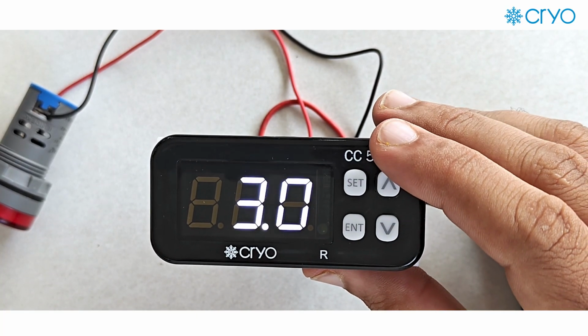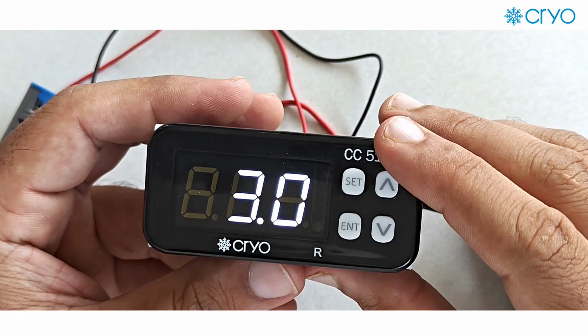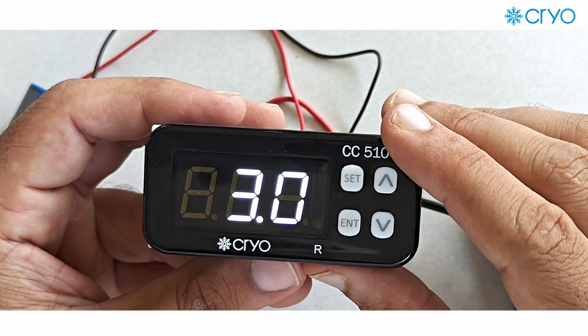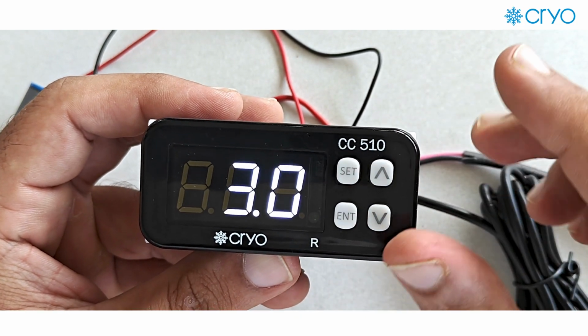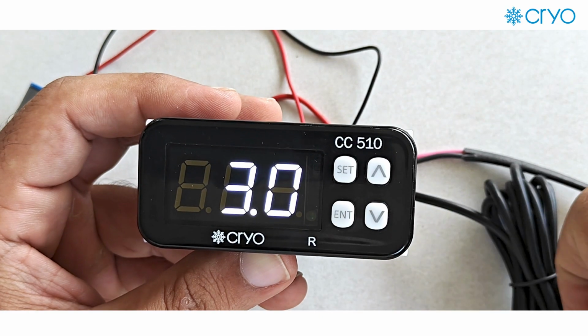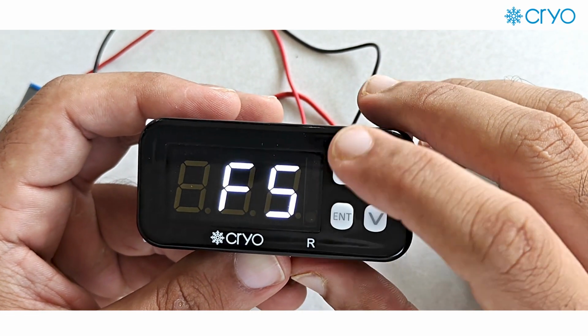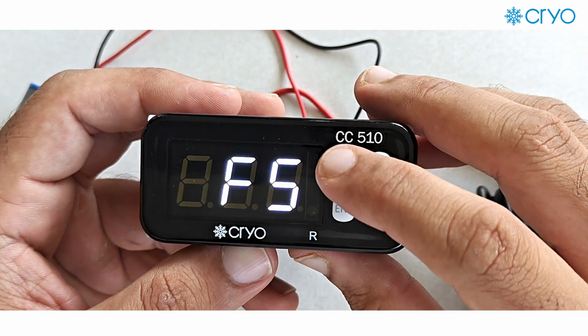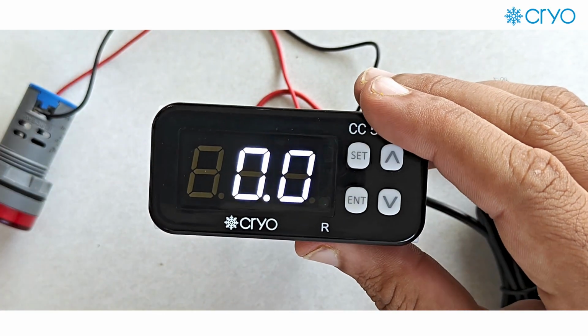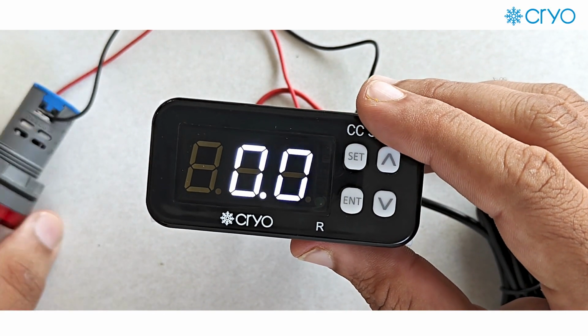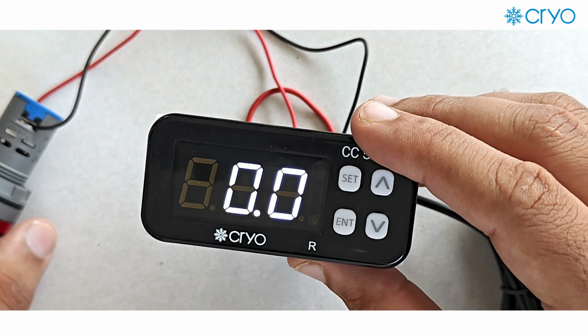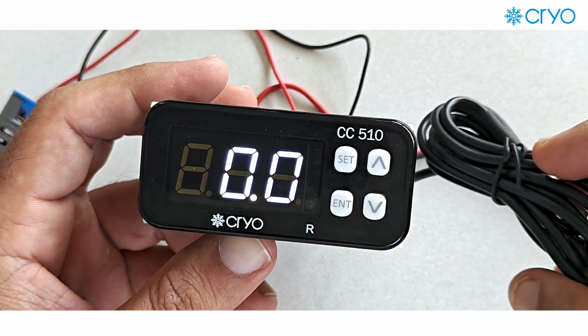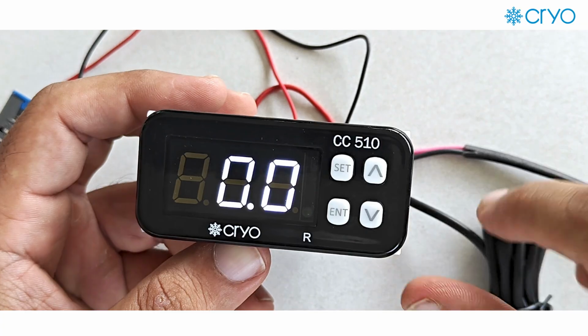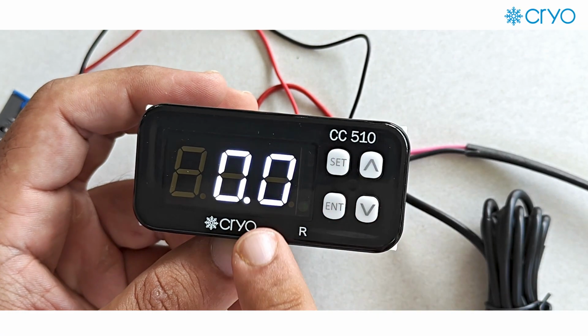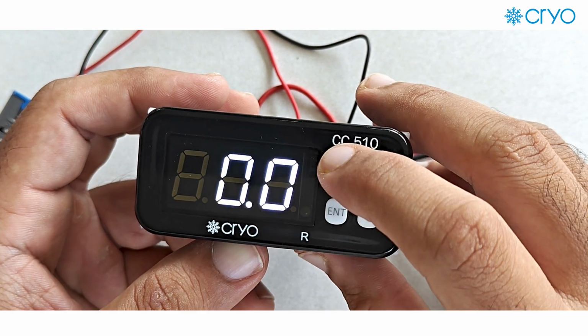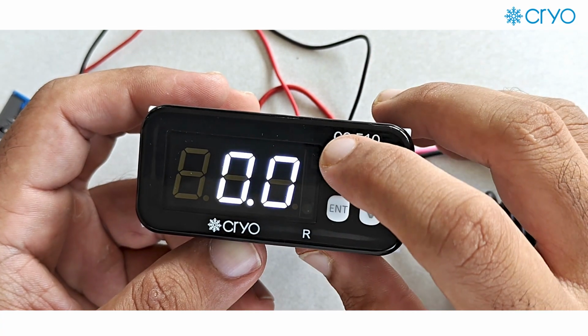Let's say my set point is currently 10 degrees Celsius. So 10 plus 3 degrees Celsius, above 13 degrees Celsius, my compressor will again get on. Again we will press set button. So F5 will come. So F5 is our offset value. So in the case of calibration, if you want the values to be changed manually, you can press up and down button and you can calibrate the sensor according to your requirement in F5 mode.